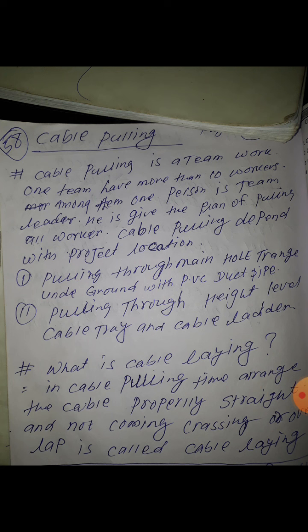As per site requirement, or as per the building system, however many systems are going there, as per the drawing, we follow this. During pulling time you must check the arrangement of the cable properly - straight, not crossing, and not making lapping there. You should make it straight, be clear about this.